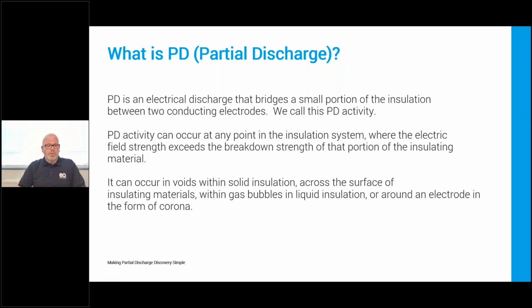So first of all, what is PD? PD, or partial discharge, is an electrical discharge which bridges a small proportion of the insulation between two conducting electrodes. We tend to refer to that, you'll hear it a lot through EA, as PD activity. PD activity can occur anywhere within the insulation system where the electrical field strength exceeds the breakdown strength of that section of the insulation material.